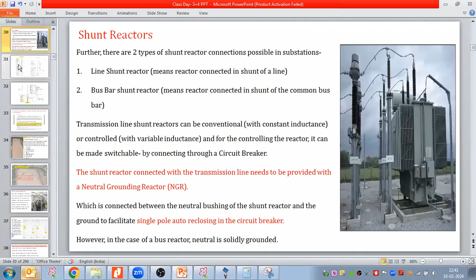However, in the case of the bus reactor, neutral is solidly grounded and the NGR is not required in case of the bus reactor. I took this statement. What is my reference of this statement? So first of all, let me show you the drawing, the SLD, and then I will come on the statement. So if you see here, this is my 500 kV transmission line. Could you see here? The bus bar I deleted here because I just wanted to focus on the line reactor.